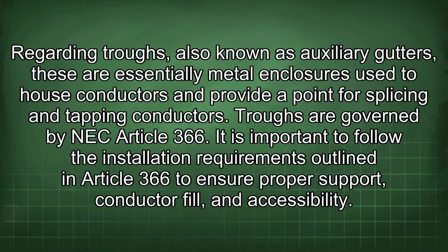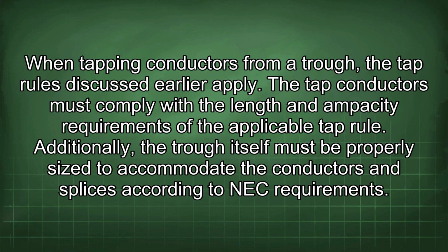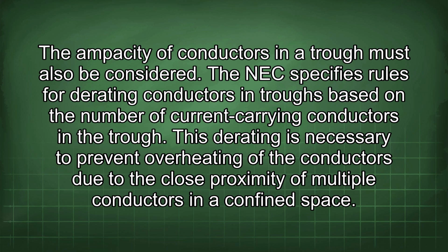Regarding troughs, also known as auxiliary gutters, these are essentially metal enclosures used to house conductors and provide a point for splicing and tapping conductors. Troughs are governed by NEC Article 366. It is important to follow the installation requirements outlined in Article 366 to ensure proper support, conductor fill, and accessibility. When tapping conductors from a trough, the tap rules discussed earlier apply. The tap conductors must comply with the length and ampacity requirements of the applicable tap rule. Additionally, the trough itself must be properly sized to accommodate the conductors and splices according to NEC requirements. The ampacity of conductors in a trough must also be considered. The NEC specifies rules for derating conductors in troughs based on the number of current-carrying conductors in the trough. This derating is necessary to prevent overheating of the conductors due to the close proximity of multiple conductors in a confined space.